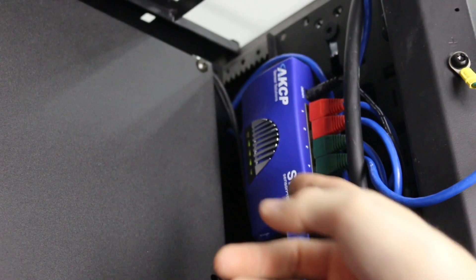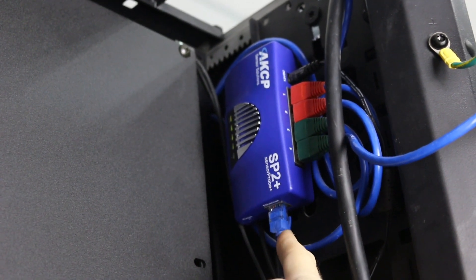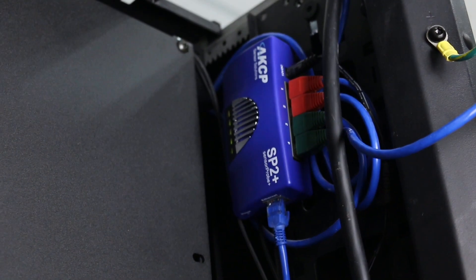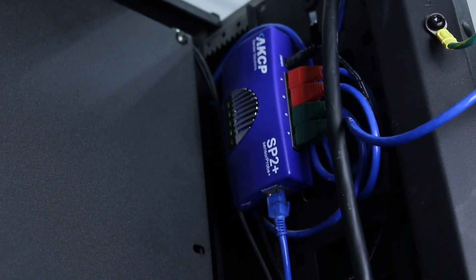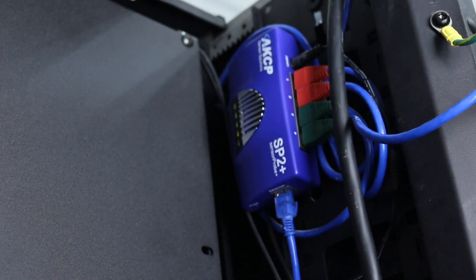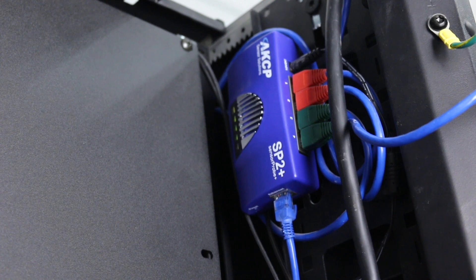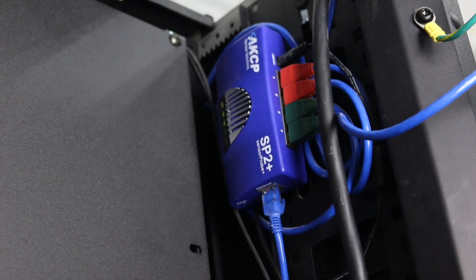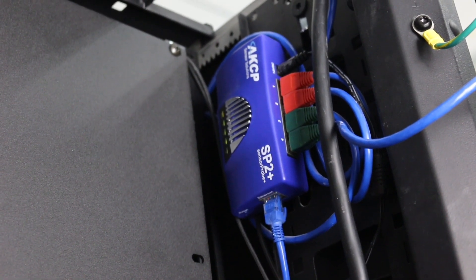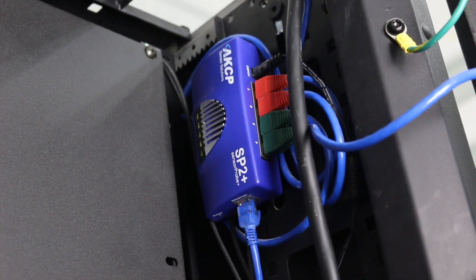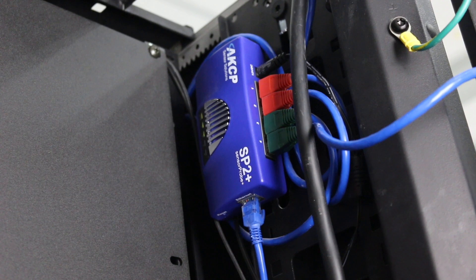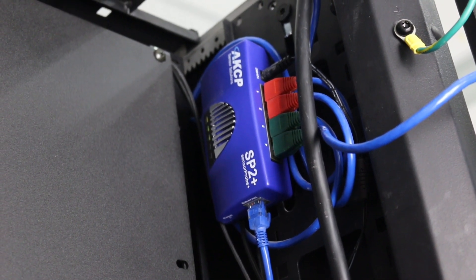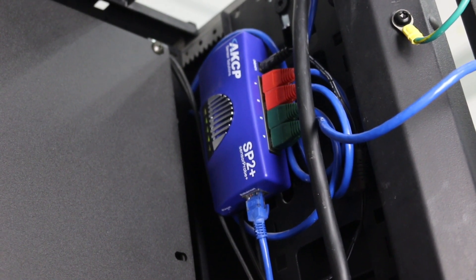Mounted in the zero U space at the back of the cabinet, we've got our SP2 Plus. We have the Ethernet connection coming in at the bottom, our power supply, and four sensor ports. The two sensor ports with red connectors go to our thermal maps, and the two with green connectors are used for our RFID swing handle cabinet locks. A wide variety of other sensors are also available from AKCP that can be plugged into your SP2 Plus. It's quite a compact unit—you can always find space inside your cabinet to mount it. It's very versatile, connecting with a wide range of sensors, and particularly in this kind of setup it's perfect for giving you a complete rack monitoring system with security and thermal mapping.